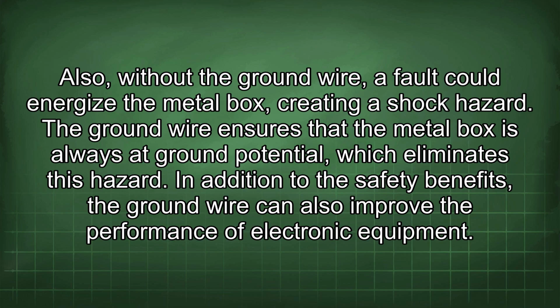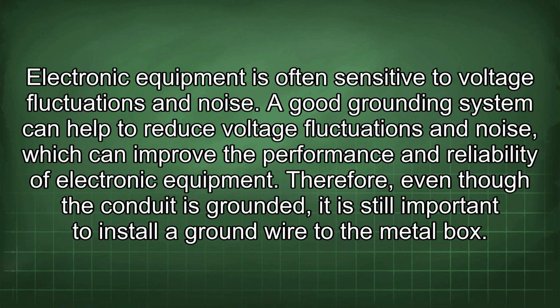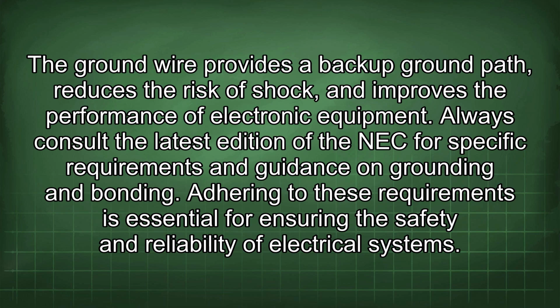In addition to the safety benefits, the ground wire can also improve the performance of electronic equipment. Electronic equipment is often sensitive to voltage fluctuations and noise. A good grounding system can help to reduce voltage fluctuations and noise, which can improve the performance and reliability of electronic equipment. Therefore, even though the conduit is grounded, it is still important to install a ground wire to the metal box. The ground wire provides a backup ground path, reduces the risk of shock, and improves the performance of electronic equipment. Always consult the latest edition of the NEC for specific requirements and guidance on grounding and bonding. Adhering to these requirements is essential for ensuring the safety and reliability of electrical systems.